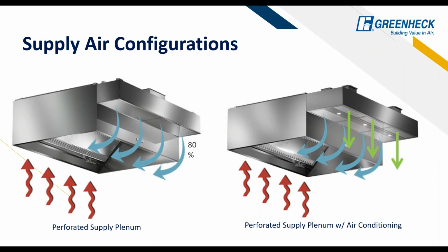Okay, and then supply air configurations. Typically you see about 80% makeup air. It's not a requirement that you have to go 80%. You can go higher, you can go lower, just depending on what balancing you might be doing within your space. But typically you just go 80%. You can supply that right at the hood and almost create an air curtain, like I mentioned.